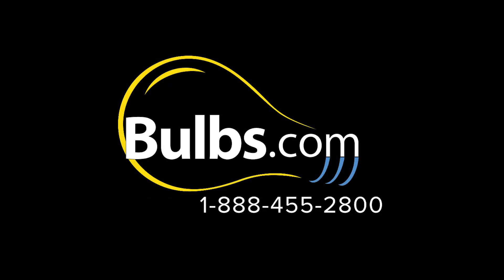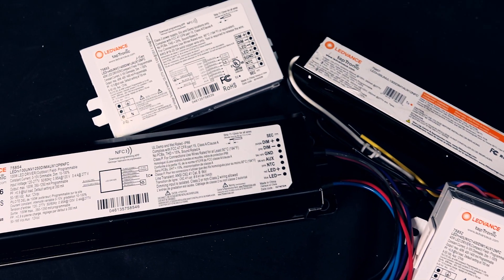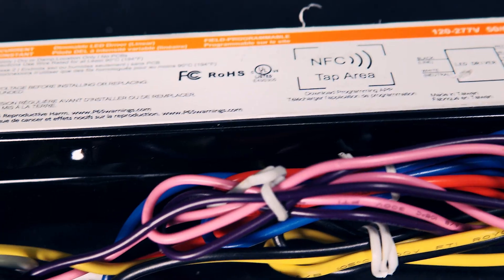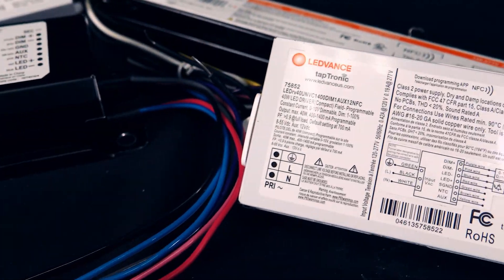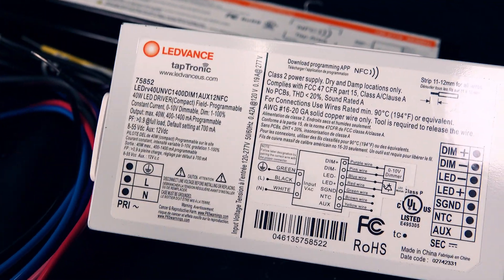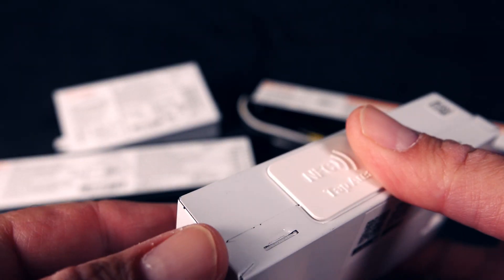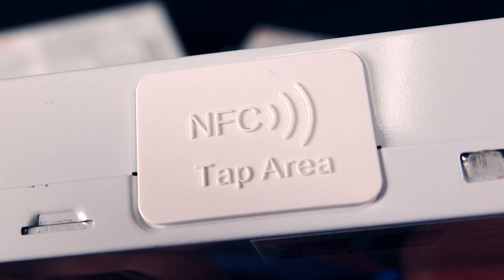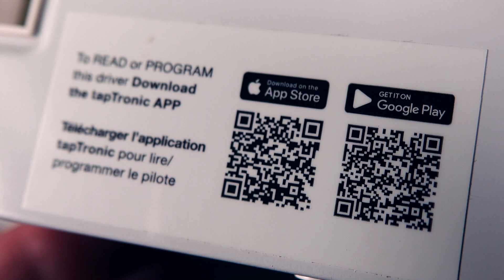The Ledvance tapTronic Programmable Drivers are an excellent, low-cost option to restore life to a failing fixture. They are constant current, dimmable power supplies that can easily be programmed in the field quickly and without a laptop or power source.